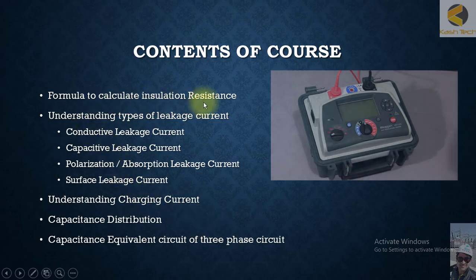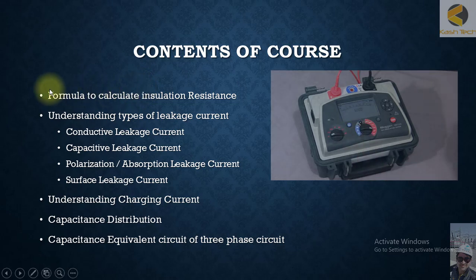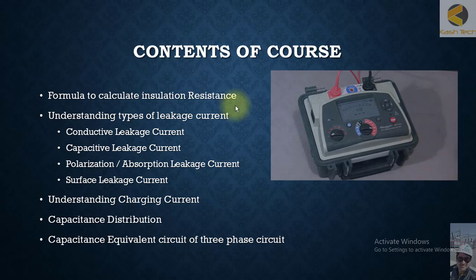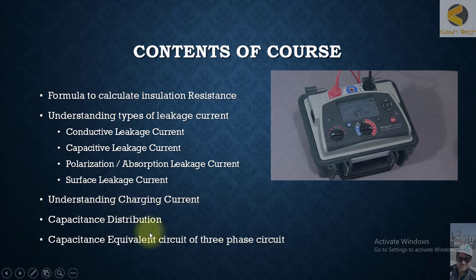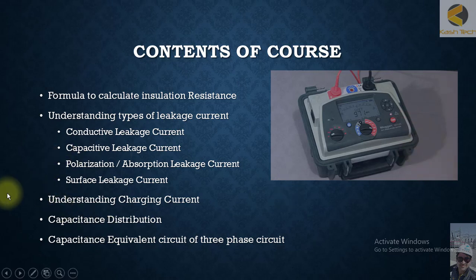We will discuss the formula to calculate insulation resistance — if you know the parameters of any cable or insulation, you can calculate the expected insulation resistance and compare it with results. We will then cover types of leakage currents: conductive leakage, capacitive leakage, polarization absorption leakage, and surface leakage currents. Further, we will understand the charging current phenomenon and capacitance distribution along the insulation.